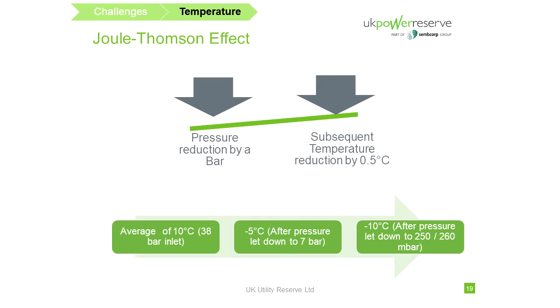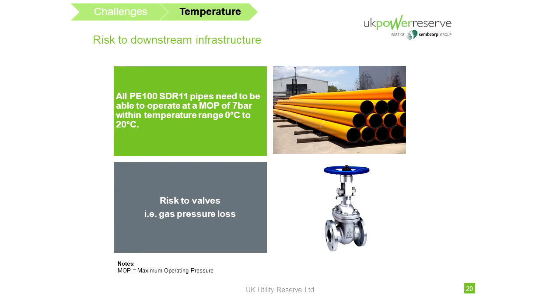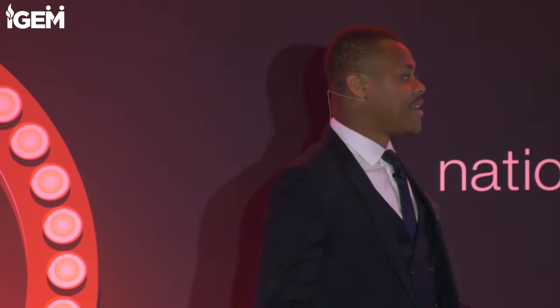Obviously, straight away, this is a high risk because I've got downstream pipe works, and the PE pipes have an operating range of between 0 degrees Celsius and 20 degrees Celsius. So that is a very key risk to the polyethylene pipes. I've also got risks to the valves, which obviously affects the gas. There's obviously a risk of a gas pressure loss.